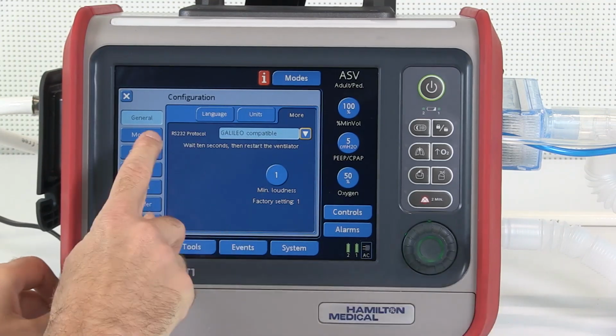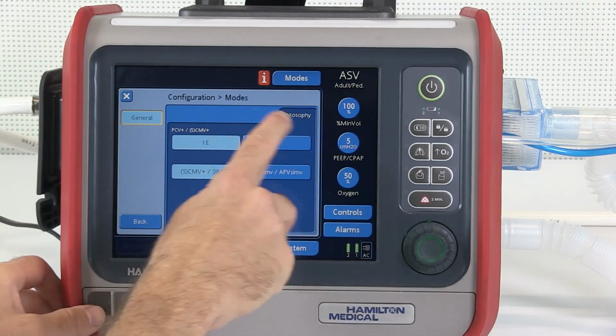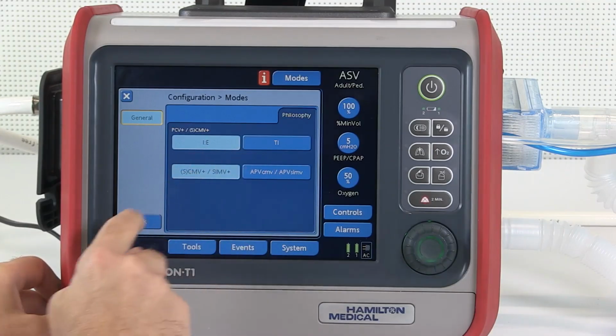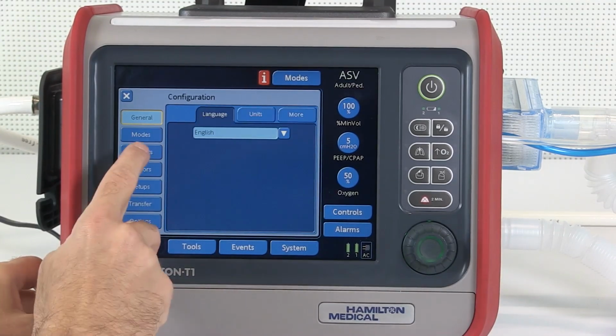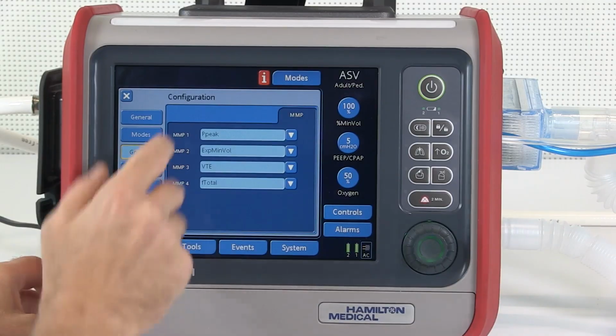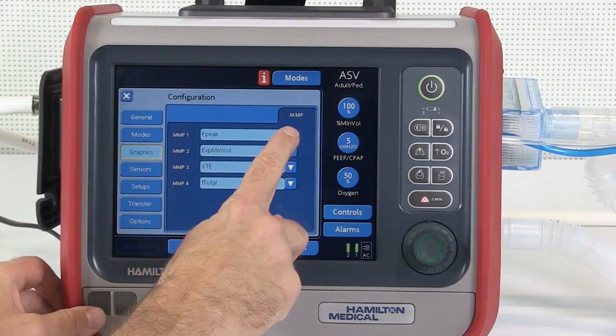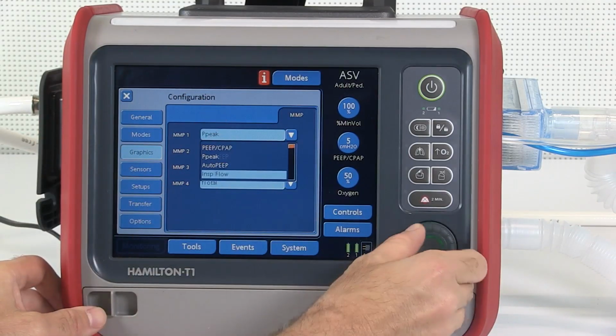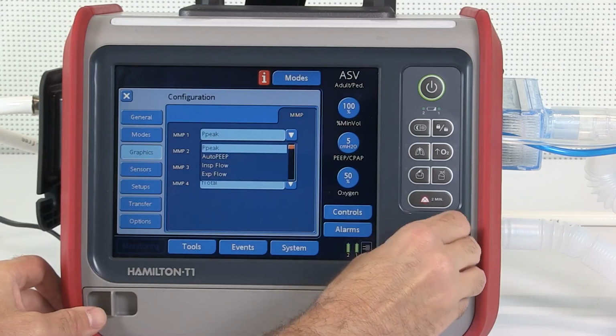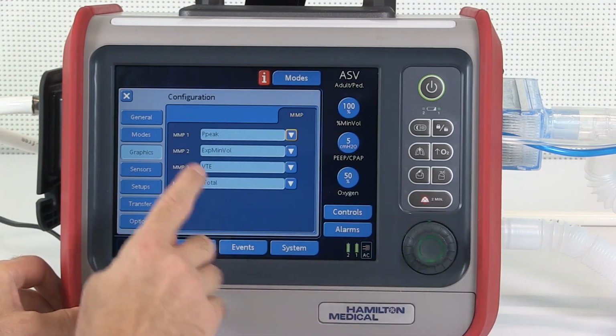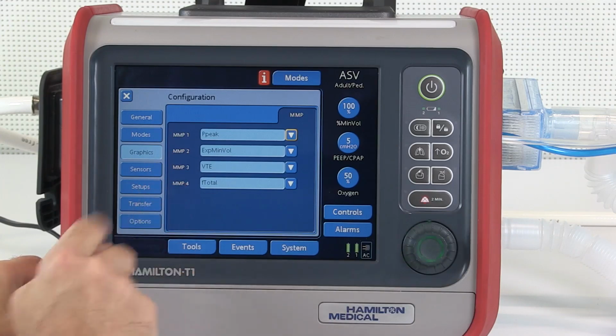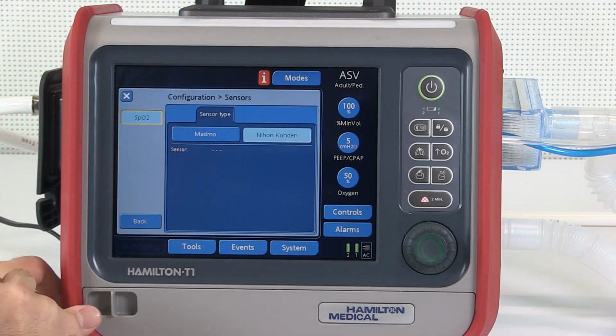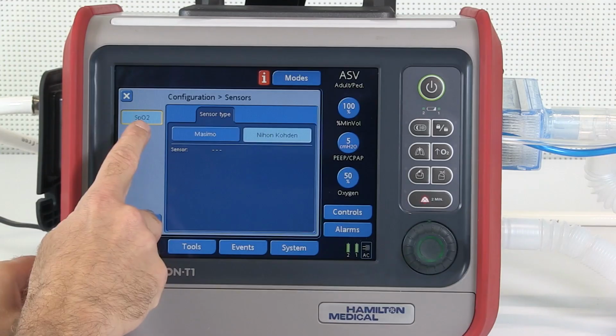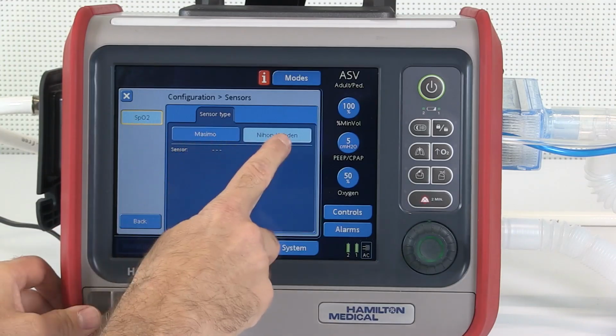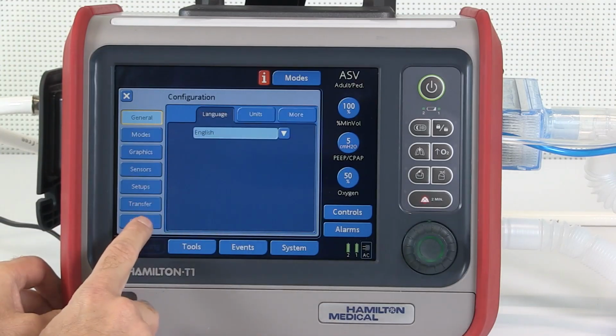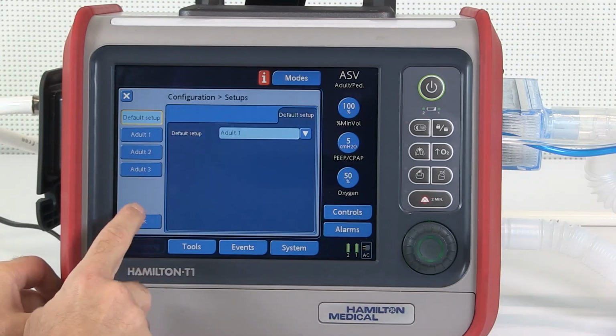Touch General to choose which mandatory timing philosophy and naming convention to use for the volume-controlled pressure adaptive modes. Touch Graphics to define a default set of main monitoring parameters that will be displayed in that position on the screen. Repeat for the remaining parameters. Touch Sensors to choose the SpO2 sensor type from either Masimo or Nihon Kohden. Touch Setups to configure individual setup settings.